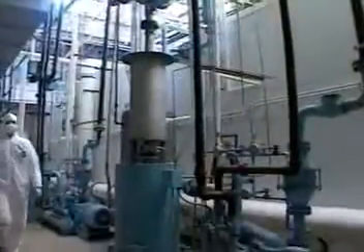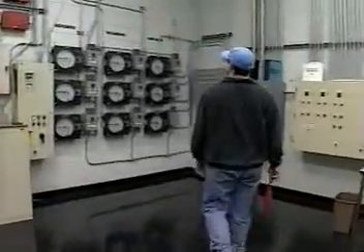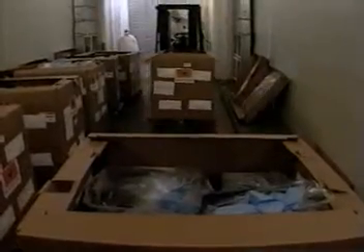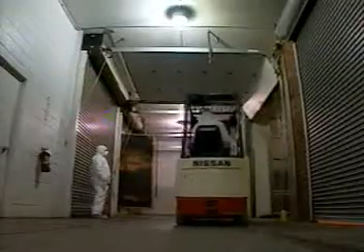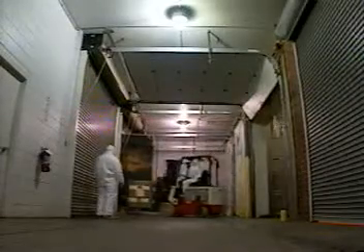The critical items are then put through a 20 to 24-hour ethylene oxide sterilization process that kills any anthrax spores in or on the items. The process is used extensively to disinfect medical equipment and clean sensitive museum artifacts and documents. The containers are first warmed in a pre-treatment chamber to bring the material back up to normal room temperature. After pre-treatment, they're moved to the sterilization chamber for a process somewhat similar to heat fumigation, but on a much smaller scale.